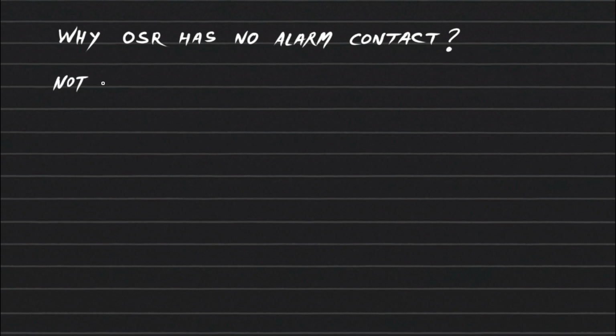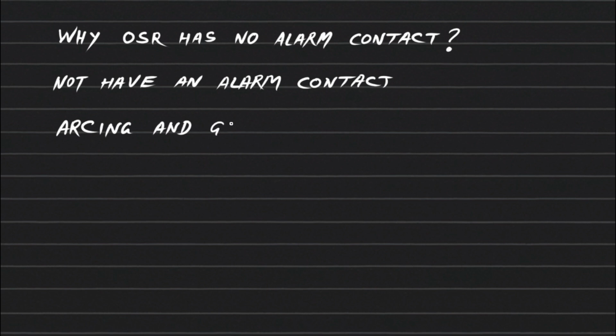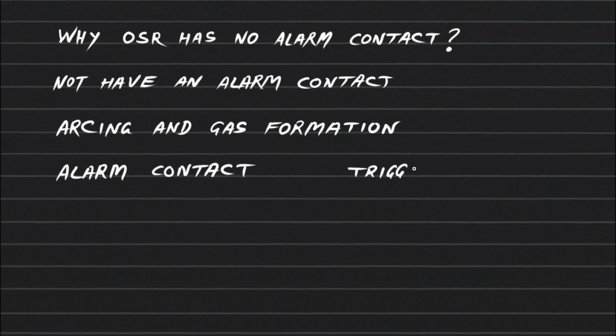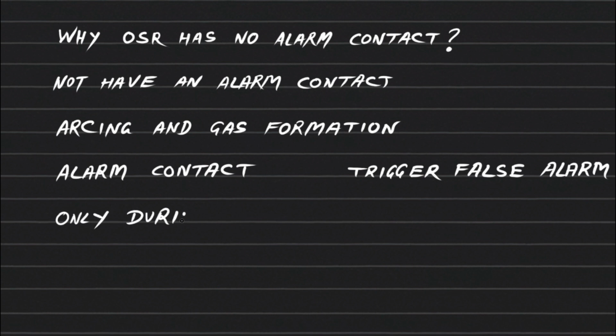Now let's answer a common question. Why does the oil surge relay not have an alarm contact, like the Buchholz relay? The reason is simple. During every tap-changing operation, a small amount of arcing and gas formation is normal inside the diverter tank. If we provided an alarm contact in the OSR, these gases would trigger false alarms, even when no actual fault exists.